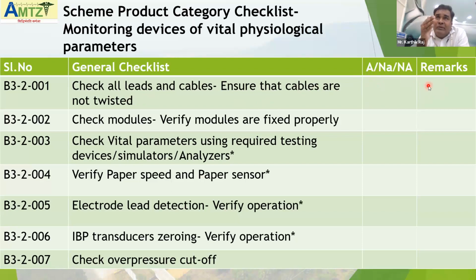Here we are trying to make sure that you can capture a failure before it comes. Usually, except for a complete, catastrophic failure, catastrophic meaning the equipment may fail all of a sudden. That happens because of a component getting damaged, maybe a capacitor getting short circuited or a resistor getting open. Except for that, all kinds of failure we can capture in advance if you follow this checklist part.